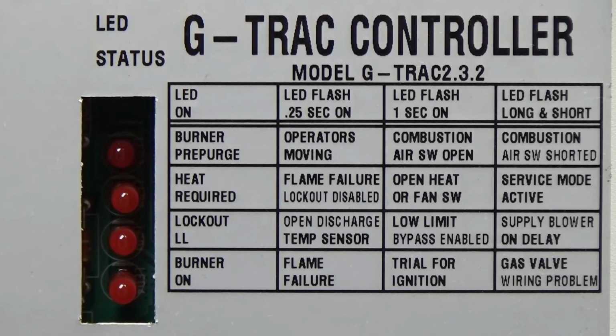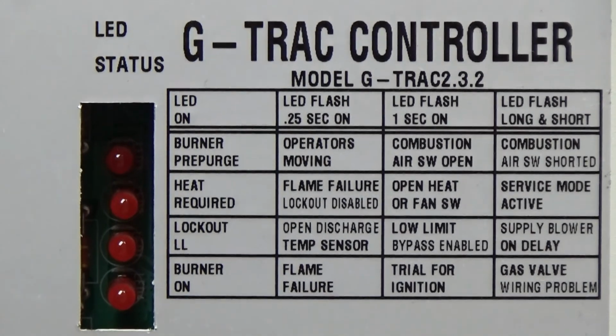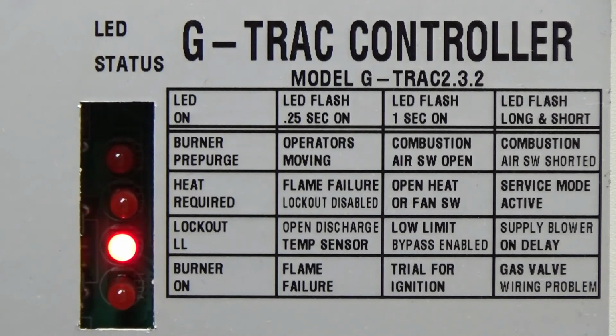The discharge air sensor is based on resistance. A resistance greater than 4,000 ohms will show up as open sensor alarm on the GTRAC2. A quarter-second LED flash indicates open discharge temperature sensor. The sensor has failed and will have to be replaced.